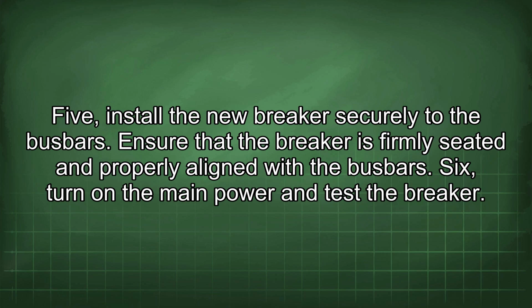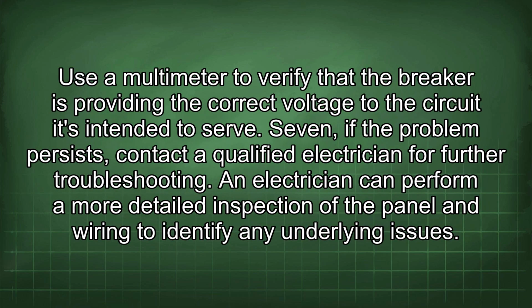6. Turn on the main power and test the breaker. Use a multimeter to verify that the breaker is providing the correct voltage to the circuit it's intended to serve. 7. If the problem persists, contact a qualified electrician for further troubleshooting. An electrician can perform a more detailed inspection of the panel and wiring to identify any underlying issues.